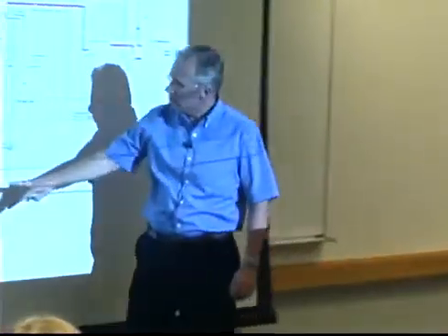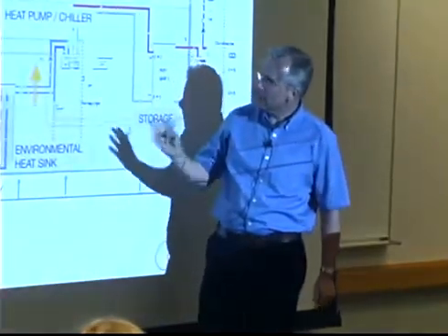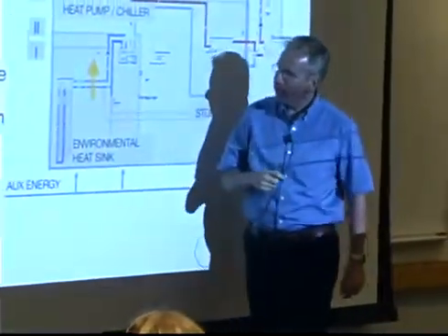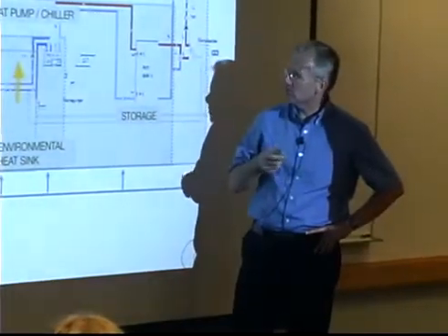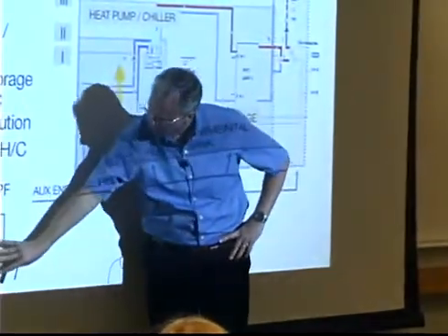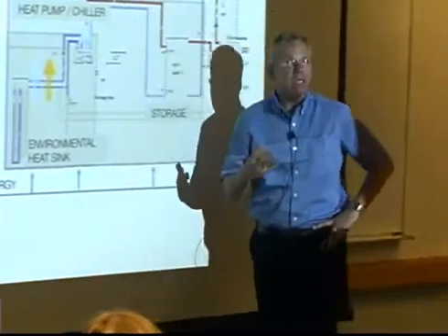And what we now simply do is we relate the amount of auxiliary energy that is required to provide that heating and cooling, that auxiliary energy, put it in the denominator, and the heating and cooling provided will be put in the numerator, and we call that the seasonal performance factor. So what you want is high values of seasonal performance factor, where you have little auxiliary energy required to provide a certain amount of heating and cooling, right?